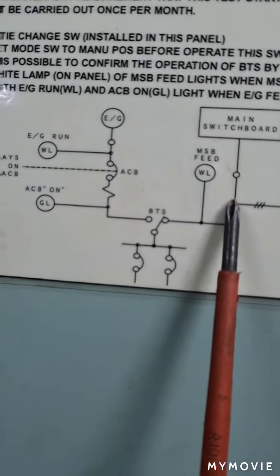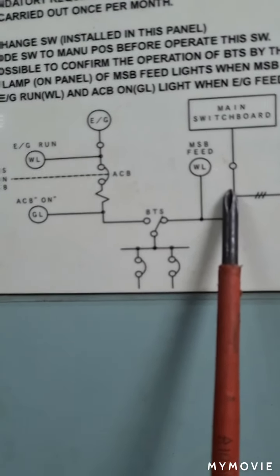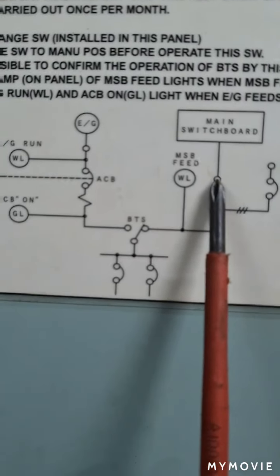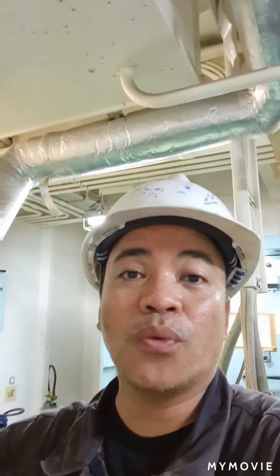But as you may take note, you need to switch on the circuit breaker here. You also need to manually switch on the circuit breaker of the main switchboard on the engine control room panel. By doing so, you can now have the shore power going to your shore connection terminal box, then from the shore connection terminal box going to the emergency switchboard automatic bus tie switch, and then from the automatic bus tie switch to the bus bar. I will show you the diagram on how all this is arranged for you to understand more.